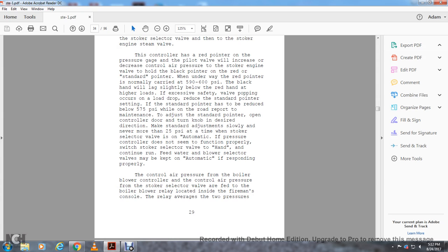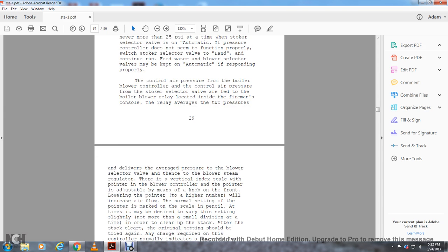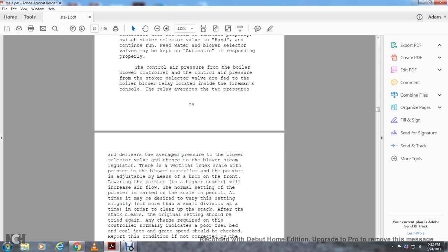boiler blower relay located inside the fireman's console. The relay averages the two pressures and delivers the average pressure to the blower selector valve, which then sends it to the blower steam regulator. The vertical index of the scale with the pointer of the blower control can be adjusted with the knob in the front. Lowering the pointer to a higher number increases the airflow. The normal setting of the pointer is marked on the scale with a pencil.